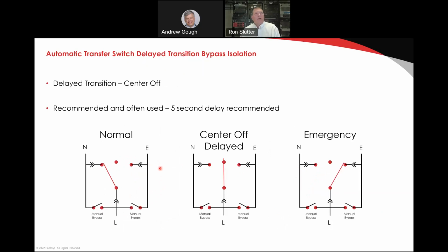Here, we're looking at what I would recommend to be most often used in the telecommunication facility. This is an ATS with delayed transition and bypass isolation. This is what you should be buying, especially for your most critical sites. We get the enhancement of having the center off position so that when we return from emergency to normal, we can let the source die before we return to normal. What is protecting the load while we're letting that happen? The batteries, whether they be the DC plant batteries, the UPS batteries, the inverter DC plant batteries, whatever the case may be, we have hours of reserve usually. Now, a couple seconds of delay here should not be an issue.